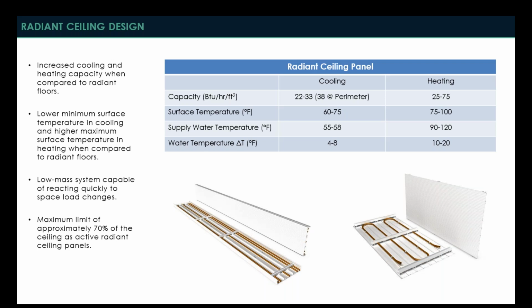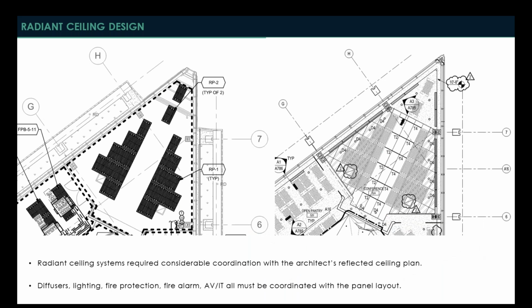There is a maximum limit, though, of how much of the ceiling you want to be active radiant ceiling panel, and that limit is around 70%. Truly, we'd like to design closer to maybe 40 or 50%, but that may not always be possible depending on the load in the space. So here you see another important example that comes into play when we're talking about radiant ceilings, and that's the concept of coordination.